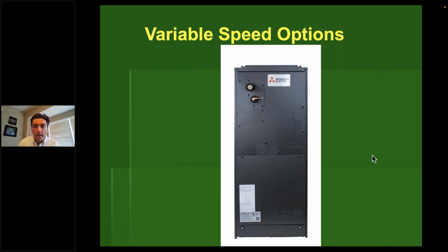There are questions about metrics. The first one from Gene: will HSPF2 give more accurate annual energy use estimates? Yes. So great question, and here's why. The whole reason the Department of Energy made this change is because they recognized that, and this is largely due to the fact that in the last 30 years, we've almost converted 100% to flex duct. And as you'll see later in one of my slides, the impact that flex duct has on static pressure in systems. And for those of you that may not be into the technical side of this, I'm going to make this really super simple. But the bottom line is that the reason that this metric changed for seasonal energy efficiency 2 and heating seasonal performance factor 2 is because the old systems were overrating the efficiency of these units with regards to how they perform in the real world.